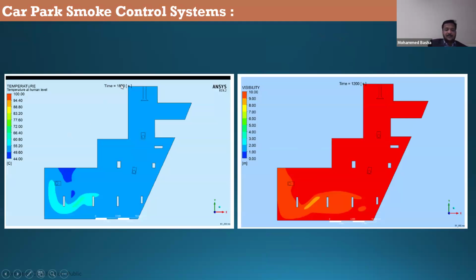Now, if you look at this here at 1800 seconds, which is 30 minutes, I have a temperature which is blue, almost 49 degrees Celsius, because civil defense says less than 60 degrees is acceptable. Visibility, I have the entire car park. So this is 1200 seconds, 20 minutes. The entire car park has 10-meter clear visibility, because my smoke extraction fans are running and jet fans are running.